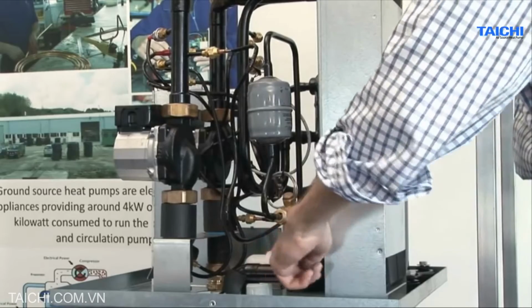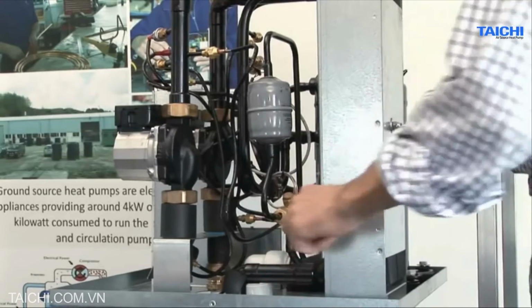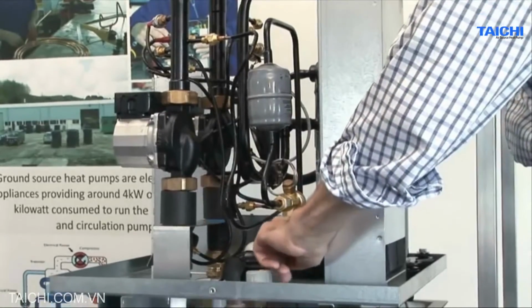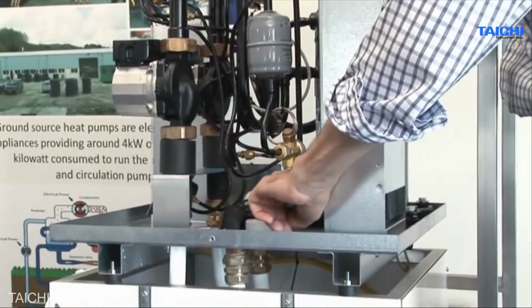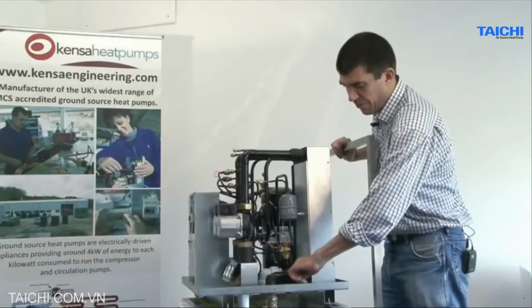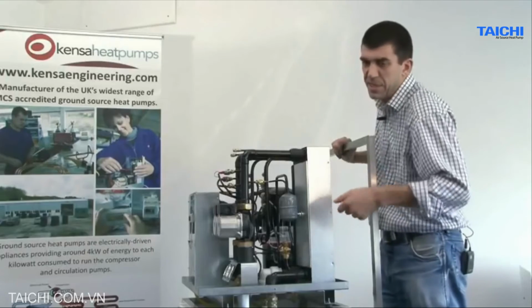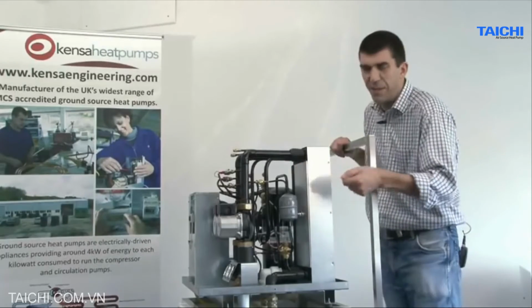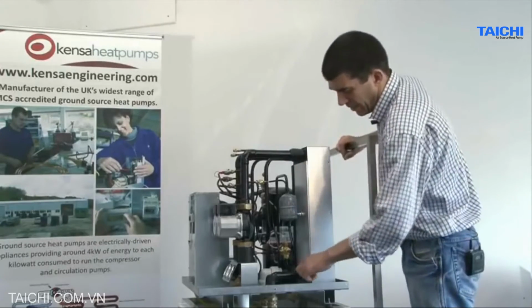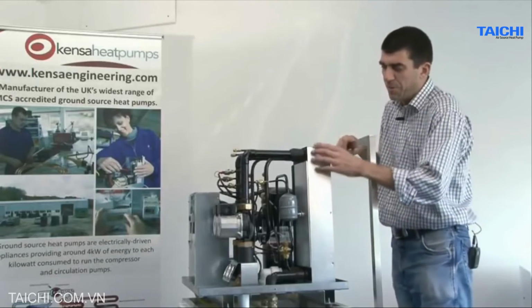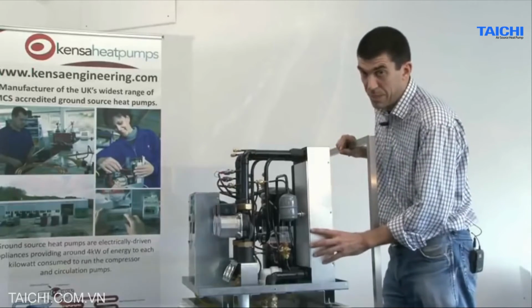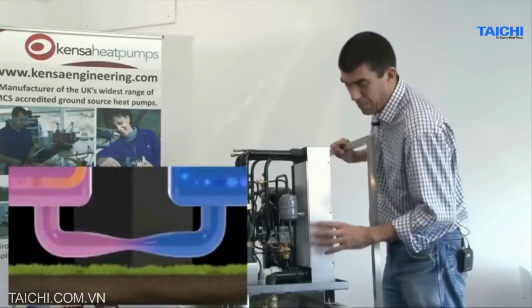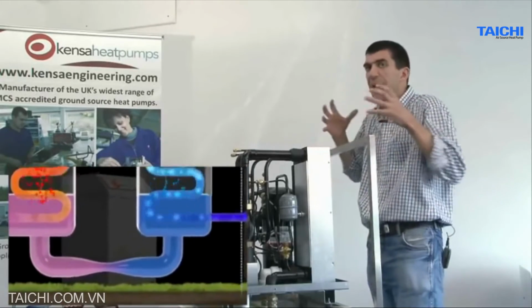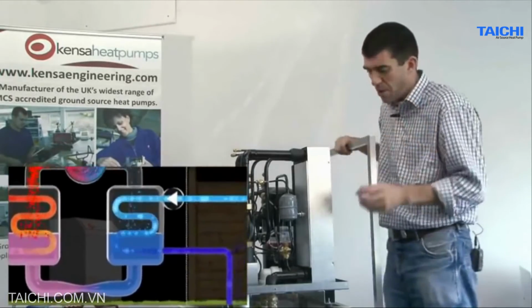The suction side of the compressor is directly connected through the heat exchanger to the outlet of the expansion valve. So this liquid refrigerant now, it's had the pressure released. It's like you've opened the valve on the camping gas bottle. And now what the refrigerant wants to do is boil, change back to a vapor. But in order to perform that function, it's got to take in heat energy. It's got to take in thermal energy.